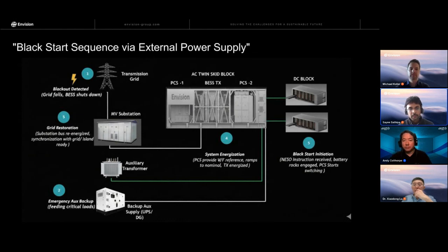You can follow the numbering sequence. When a blackout happens, usually the grid fails and the BESS shuts down, and the next thing you would need immediately is that all the systems will be running on UPS backup in their individual equipment. However, that will be for a specified duration, and you would need an emergency backup also, if we don't receive the instruction from NESO within 2 hours, because they can ask us to connect or restore the system within a duration of 2 to 72 hours.